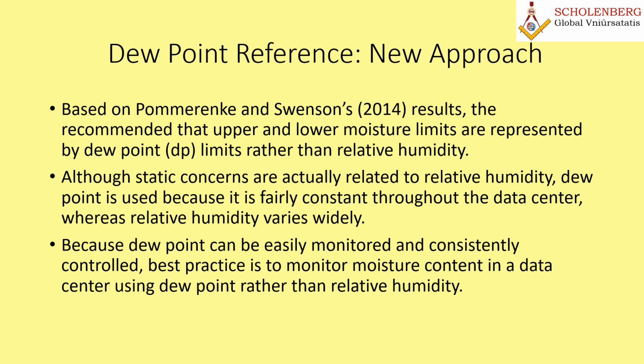Well, this particular slide is again a repetition of what we said just now: based on the Pommerenke and Swenson study, they recommended the upper and lower moisture limits as we have seen in the previous slides. The static concerns are actually related to relative humidity, and dew point is used because it is fairly constant. As we said earlier, relative humidity should not be considered as far as static electricity discharge is concerned. But dew point can be easily monitored and fairly controlled. The best practice is to monitor the moisture content in data centers using dew point rather than RH, because RH can be misleading sometimes, but dew point cannot be misleading. So from the dew point we can easily calculate how much moisture content is in the air. So I think that is a fairly accurate measure.